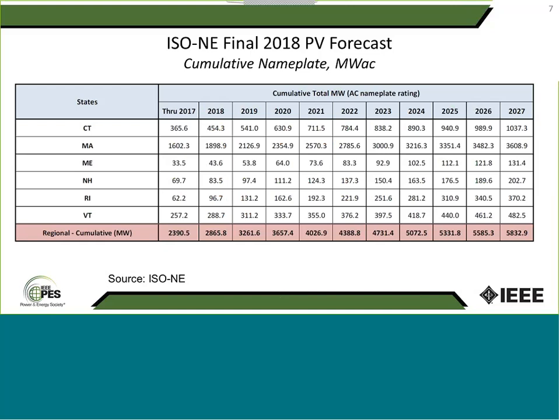So the next slide, this is the projected PV growth in different states in New England, and of course the highest is Massachusetts, and that's where ISO New England started this outreach and informing the utilities in the state that we need to do something with ride-through especially. So you see that by 2027 we're expecting to see 3.6 gigawatts of solar only, and in total for the New England area we're at a projection of 5.8 gigawatts. And the trend that we have seen so far, the actual PV growth in New England is higher than ISO's projected PV growth. So the numbers you see here, the actual PV growth is going to be a bit higher than what you see in this table, which is basically worst case from a ride-through perspective. So moving on.